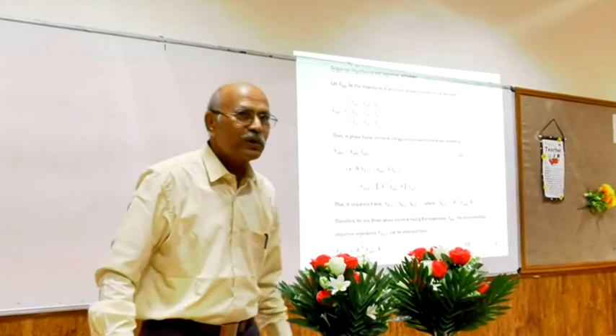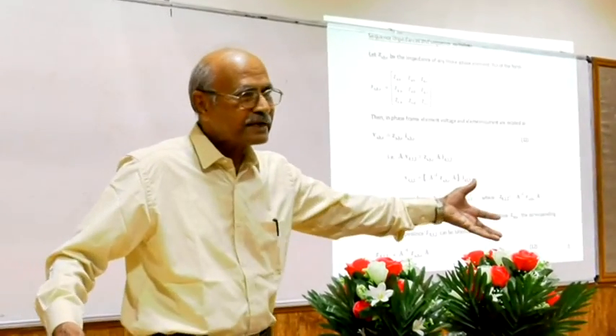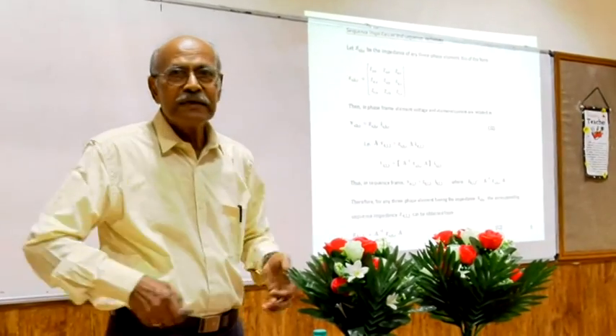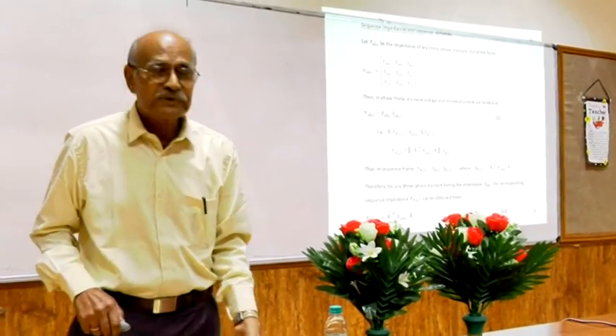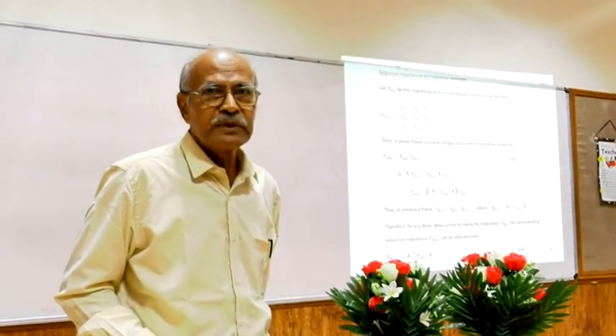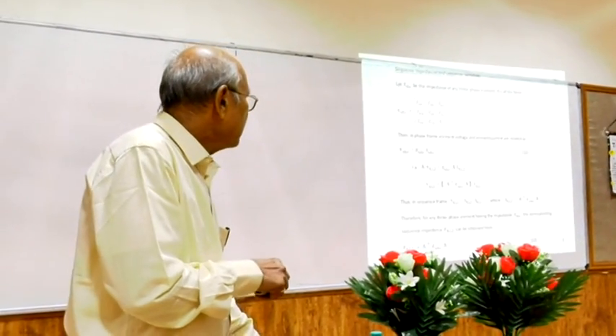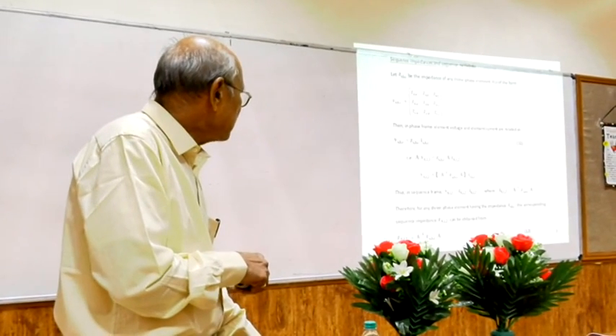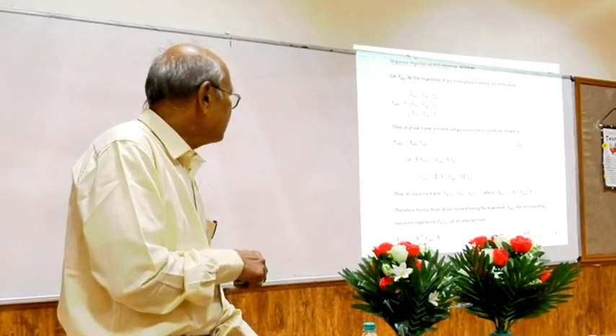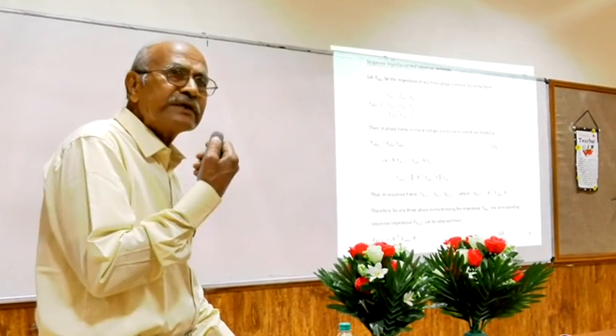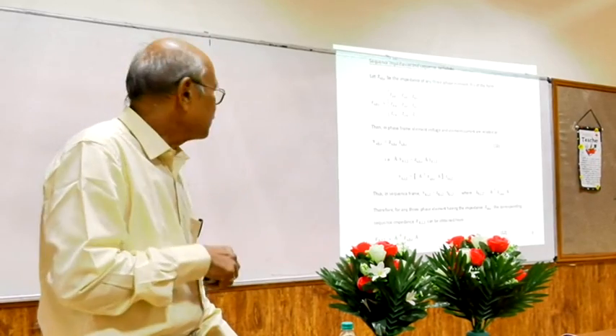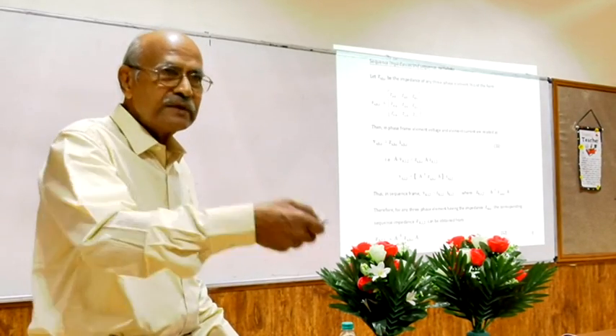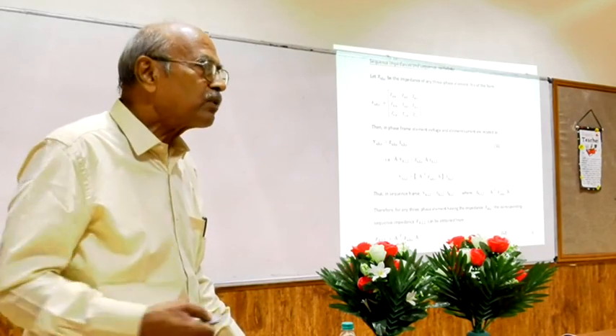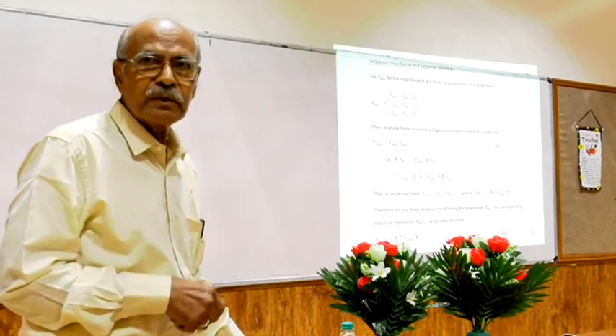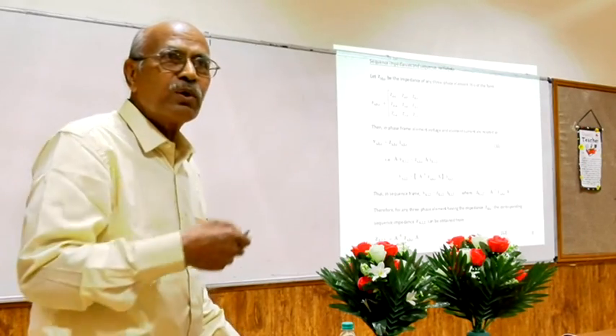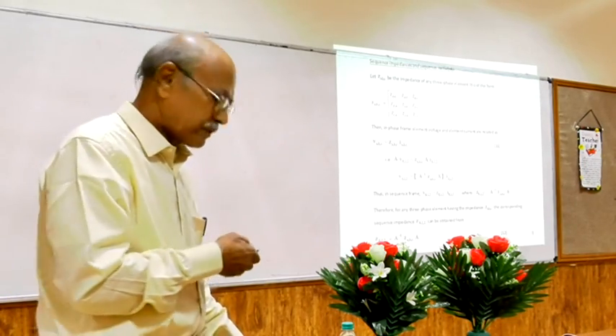I have voltage and on the other side current. In between I have some parameter, which is nothing but the zero sequence impedance of the three-phase element, the sequence impedance of the three-phase element. So I can say this is nothing but Z012, which is nothing but A inverse Z_ABC into A. A is the A matrix, I know. And if you give me what is Z_ABC, that is in the ABC frame, I can immediately find out the corresponding sequence frame impedance. Okay, so just like voltage and current, I can go either direction using the transformation.